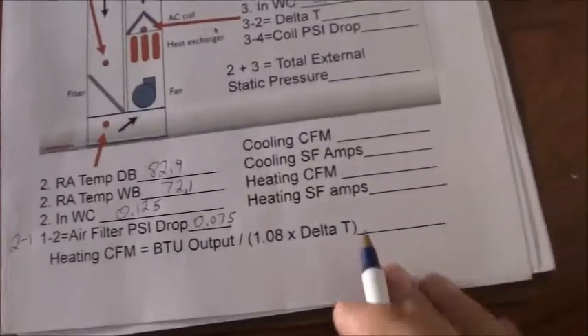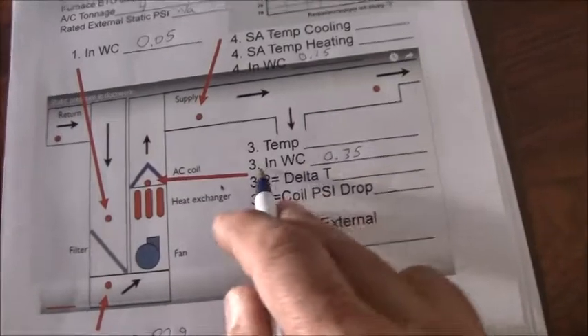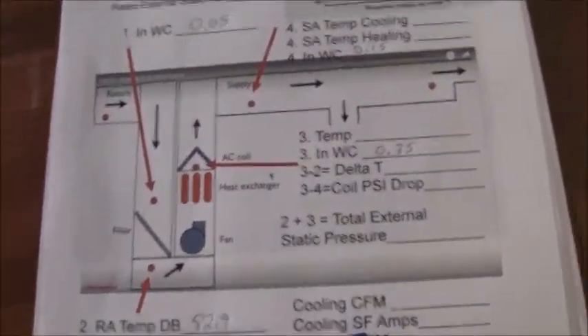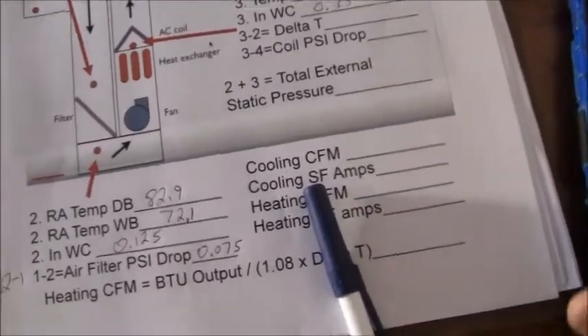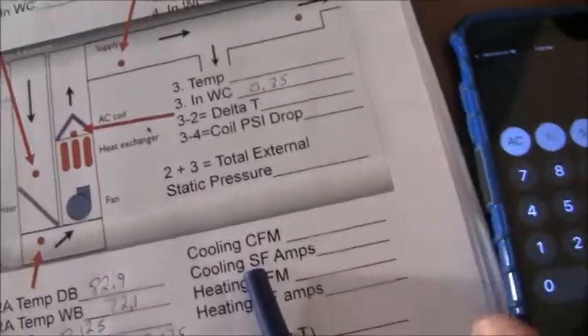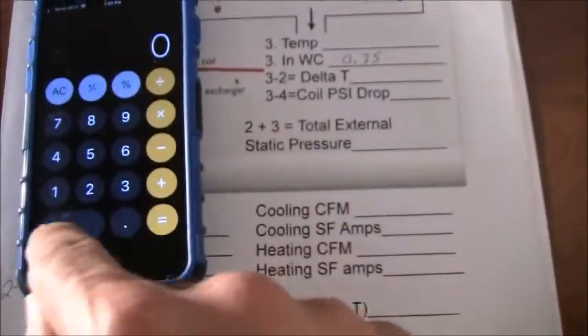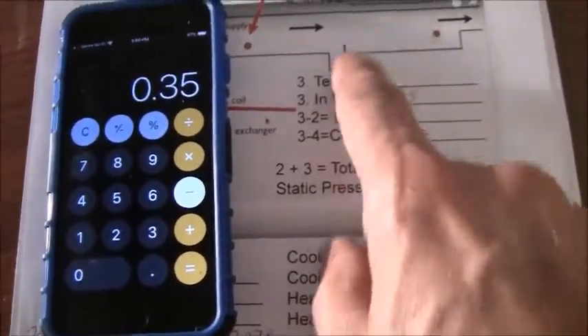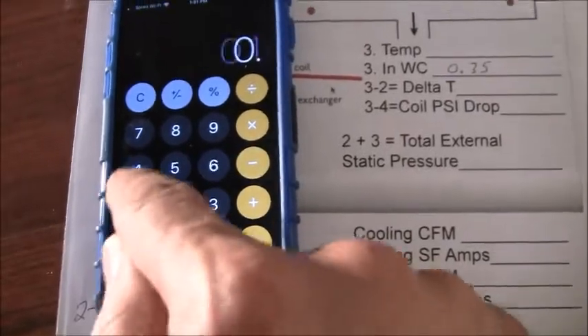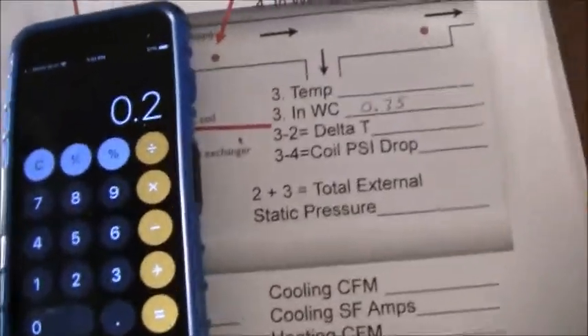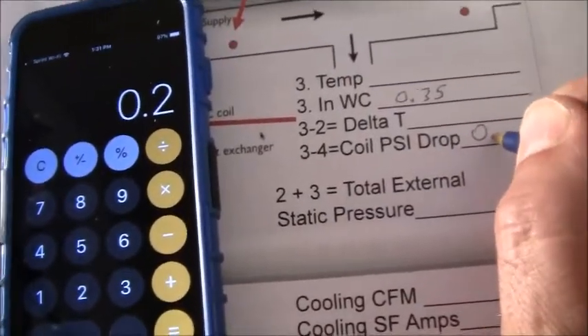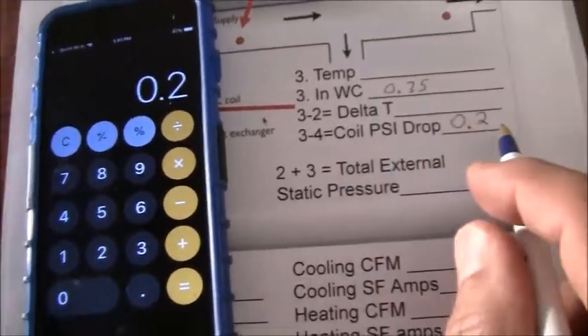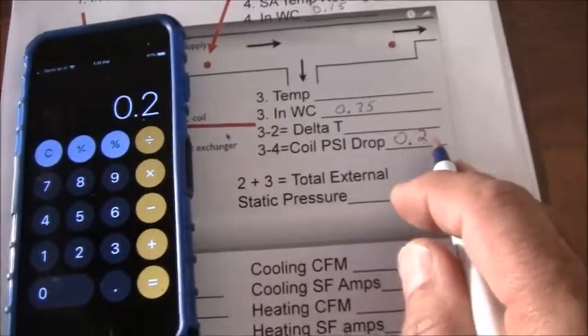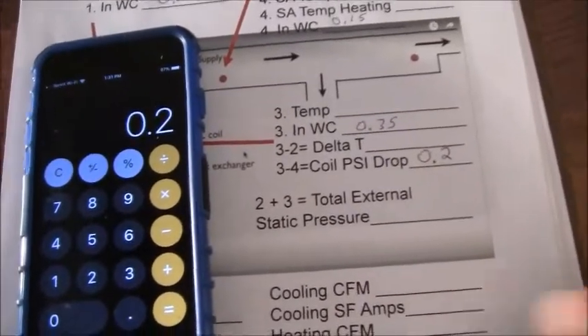0.15. Now, we can determine the coil pressure drop by taking point 3 and subtracting point 4 from it. So let's go ahead and do that, just like we did the other one. We're going to take point number 3, 0.35. We're going to subtract point number 4, which is 0.15. That's going to equal 0.2. So we know that the coil pressure drop is 0.2 inches of water column. So that's not a bad pressure drop across the coil. The coil is not plugged, where it's producing a restriction of airflow.